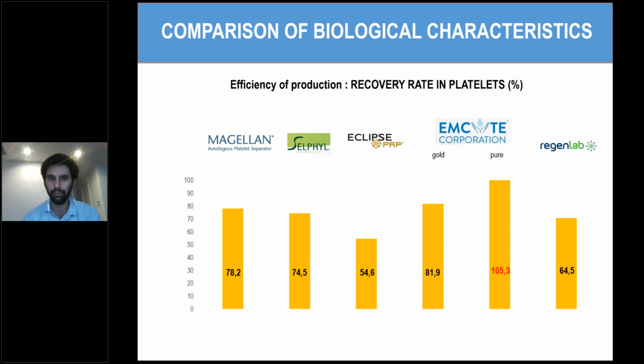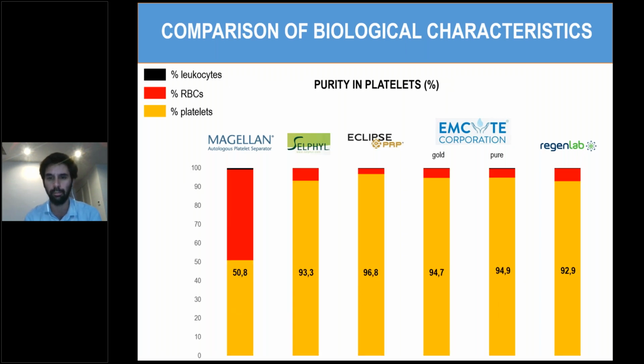The second very important parameter for us is what we call the efficiency of production. So we have a look at the recovery rate in platelets. So what was the ability of my device to recover the maximum of platelets? You can see that it varies from 54.6% with Eclipse to more than 100% with the EmCyte Pure. So I will come back to that because normally it's not possible to obtain a recovery rate higher than 100%.